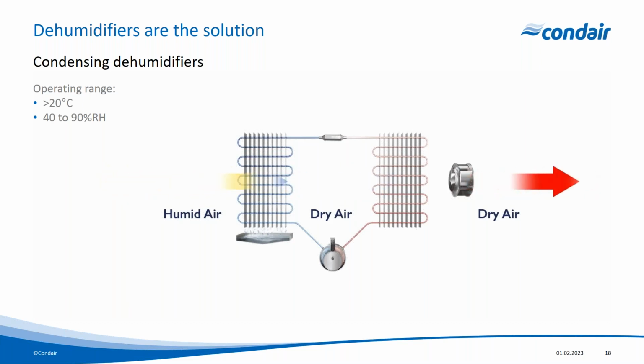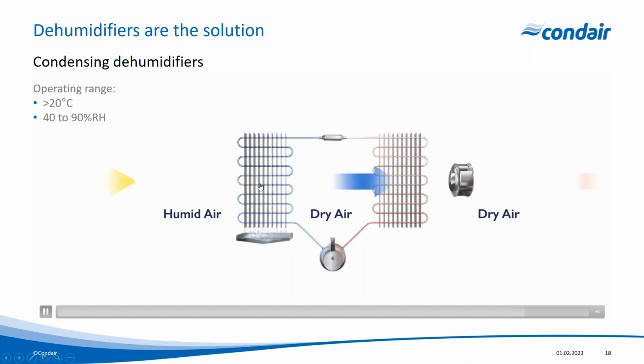But if we were to use this type of system in a cold store, we've got one mega problem, which is that it would freeze in exactly the way that we see ice forming on an evaporator. So we can only really effectively use condensing dehumidifiers when our operating temperature is much higher and we're at a higher level of relative humidity. So we've got to think of another way.